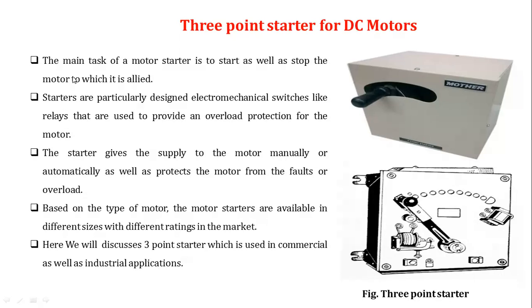Actually, starters are used to start the motor in a safe manner, because the motor has the tendency to draw a large initial current at the time of starting. So to prevent such an overload of voltage and current in the motor, we must use a starter to start the motor.